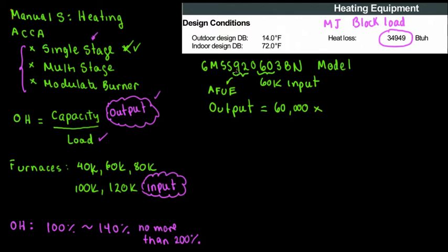In Goodman, that means this is a 60K furnace, 60K of input capacity, and this 92% represents the AFUE. For the calculation, we don't need the input, we need the output. The output is going to equal 60,000 BTUs per hour times the AFUE, which is 0.92. That's 55,200 BTUs per hour. This is the output capacity.